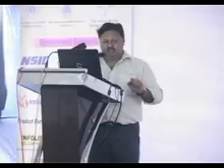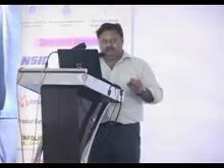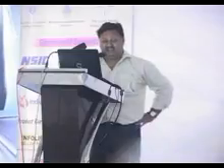So what do I infer from that? Has it lost an oxygen or has it lost an NH2 group? Because both of them have a mass of 16. So if my instrument does not have the capability to measure the fractional masses, I will not be able to tell whether I've lost a 16 or I've lost an NH2.